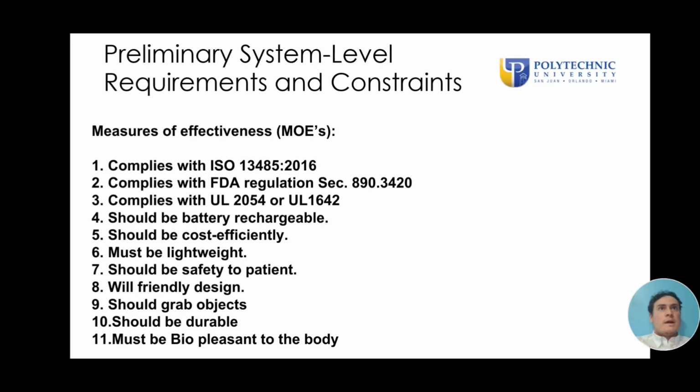We have to comply with UL 2054 and UL 1642. In the case of medical devices using batteries, manufacturers can now use the proof of compliance with UL 2054 and UL 1642 as evidence of a device's safety and effectiveness.